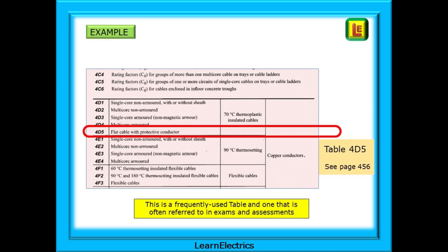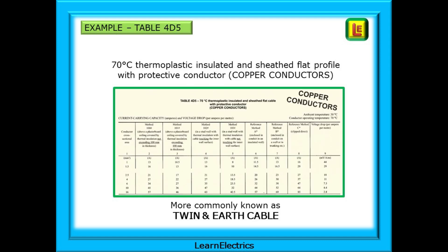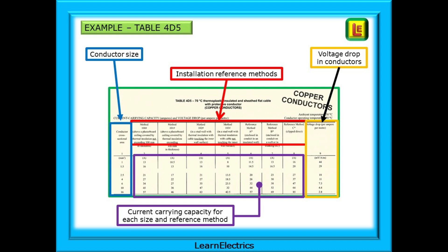Take Table 4D5 as an example. This is a frequently used table and one that is often referred to in exams and assessments. This table is listed at the top of page 575 in Table of Tables and directs us to page 456. The title of this table is 70 degrees Celsius thermoplastic insulated and sheathed flat profile with protective conductor, copper conductors, and more commonly known as twin and earth cable. If you're working in domestic properties, you may be referring to this table all the time.